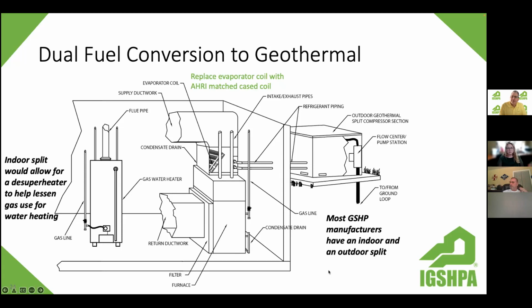So even though it's not fully electric, it is a step in the right direction, and it gives that customer the ability to use geothermal most of the time. If we decided to go with an indoor split, we could certainly connect to this water heater. We'd want a preheat tank so we could heat some water before it goes into the gas water heater, again, decreasing some of that gas use, which is going to be more important as we start to see gas prices continue to rise. So keep this in mind as an option for dual fuel conversions.